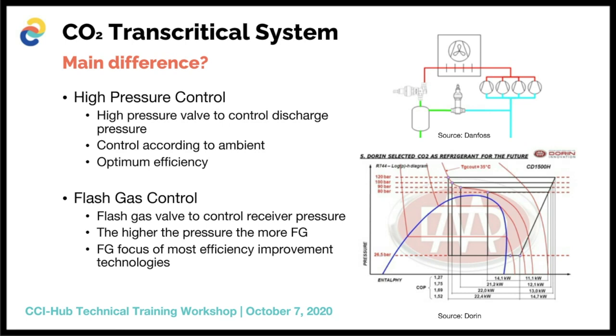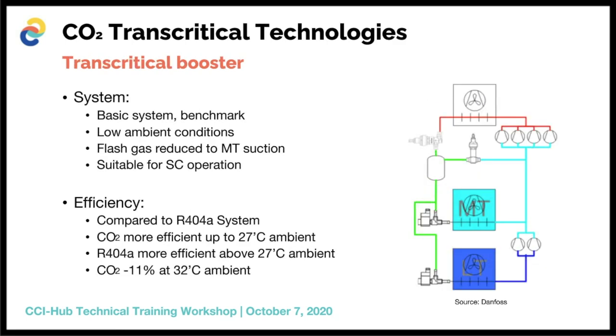So then going into some technologies that can be found. Basically your standard system that was the birth of CO2, if you want to call it that, is your basic straightforward transcritical booster system. This system basically, like I said, has the high pressure valve and the flash gas valve that's additional to what would be seen in conventional refrigerants, and therefore the rest of the system will operate in the same way. So this is a very simplistic way to have a CO2 system operate. This type of system is suitable for subcritical applications, especially when it comes to efficiency of the system. So this system will be mostly seen in lower ambient conditions where you have predominantly colder areas and not very extremely high summer conditions, so Northern Europe, Northern Americas, is where you will see this system operate.